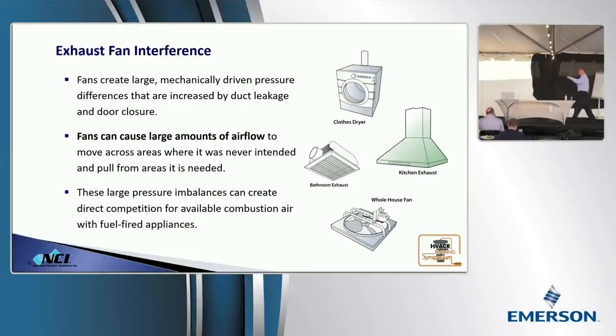John, you're on the fire department. Have you ever heard that they'll say, you know, open a window if your CO alarm goes off? Okay, has anybody else heard that? CO alarm goes off, open the windows. What if the windows that you open are on the upper part of that neutral pressure plane where exfiltration's happening, and it's a combustion air issue related to the building that's causing it? Does it get better or does it get worse? It gets worse. You just ramped up how fast that family's going to get poisoned.